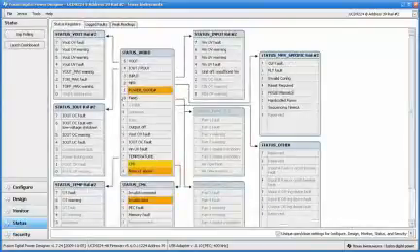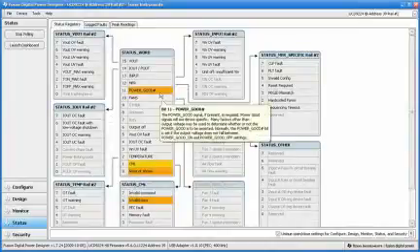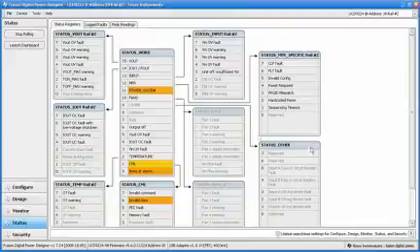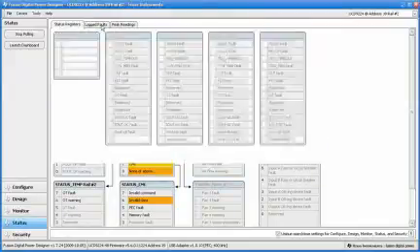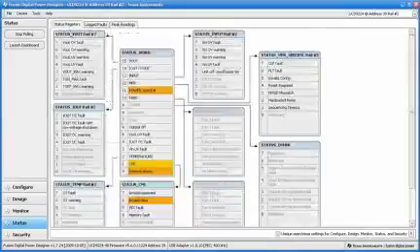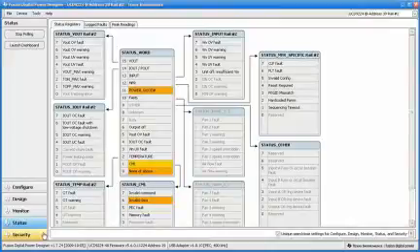So status will tell you information about the power stage itself. Are there any faults that weren't cleared previously? This will store this information into the device. Here is logged faults. And then it'll also show information on peak recordings for you, so you can read that information back at a future point in time via PMBus.